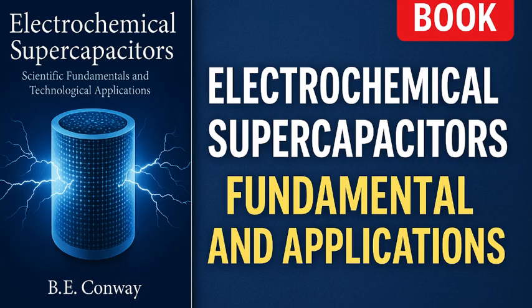Power density, in watts per kg or watts per liter. This tells how quickly that energy can be delivered. Equivalent series resistance, the internal resistance in ohms. A lower internal resistance or ESR means higher power capability and less energy lost as heating during fast charging and discharging. Cycle life. How many cycles of charge and discharge the device can endure with minimal degradation, often until 80% of the capacitance remains. Self-discharge rate. How quickly it loses voltage when sitting idle, often given as a time to drop to a certain percentage or a leakage current in microamps.